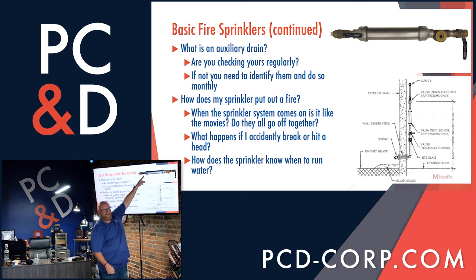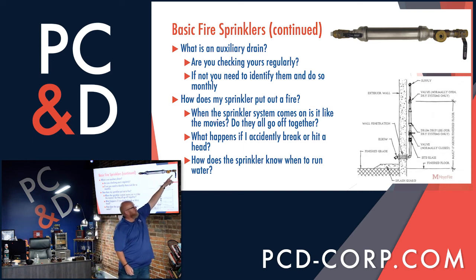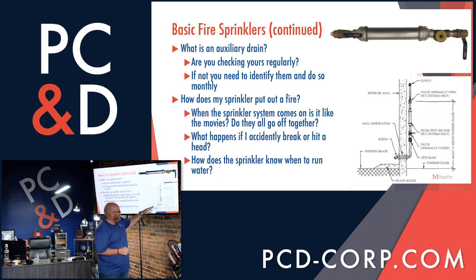I'm going to close this ball valve to isolate my dry system, then I'm going to open the other valve. What that looks like will be right here. This would be the valve that I close. This then would be the valve that I open. All of the water now from this point will drain out and go outside your building.